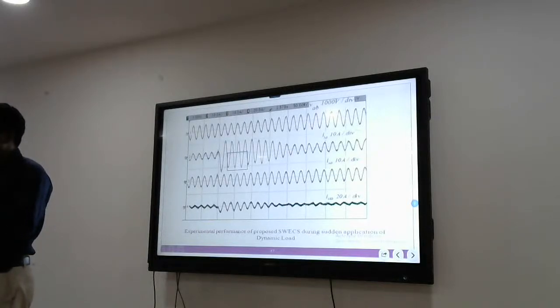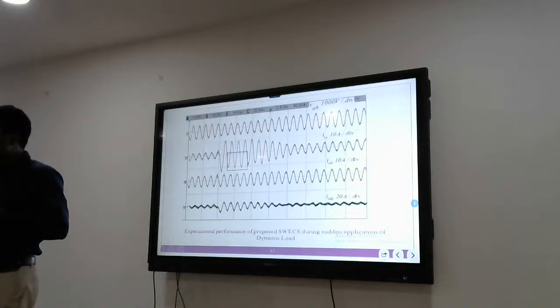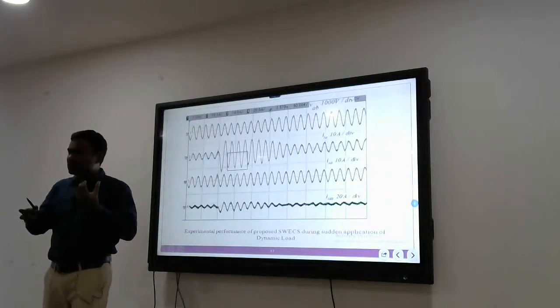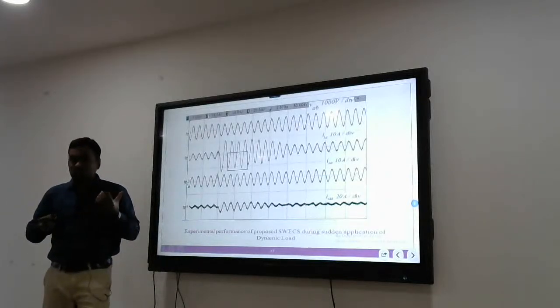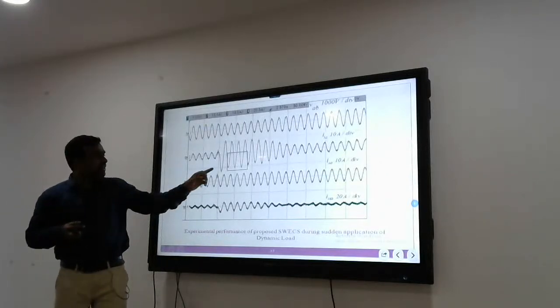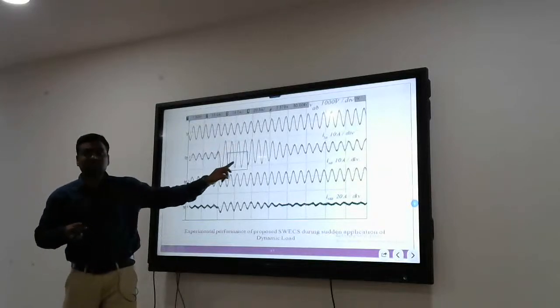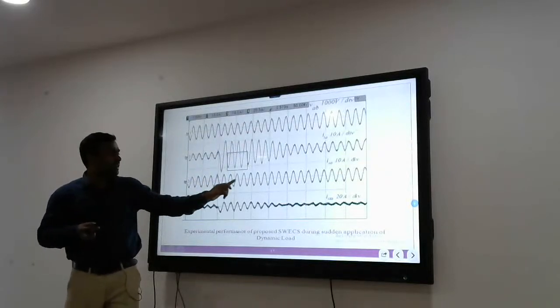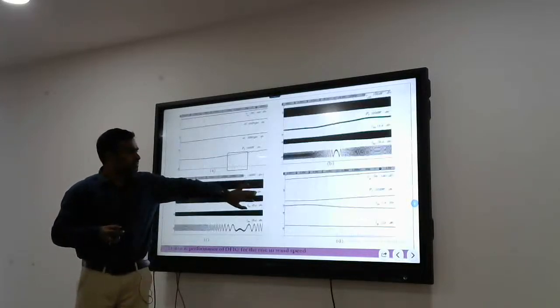Will not have much starter type of arrangement. These are quarter HP, small HP motors, you will run on DOL, direct online starting. If you do direct online starting of induction machine, you will have high inrush current. If you have that much high inrush current, if you are taking from this, your voltage may collapse. So we try to check here, the motor was turned on, still your voltage and current was maintained.